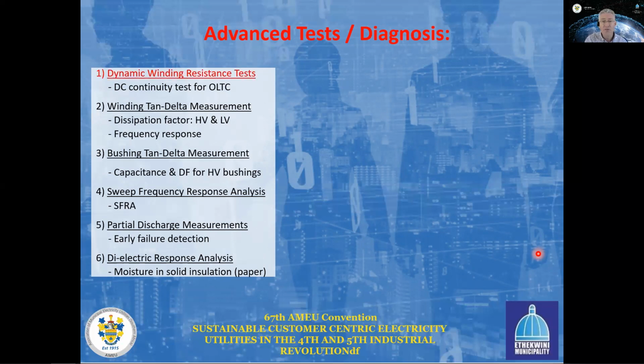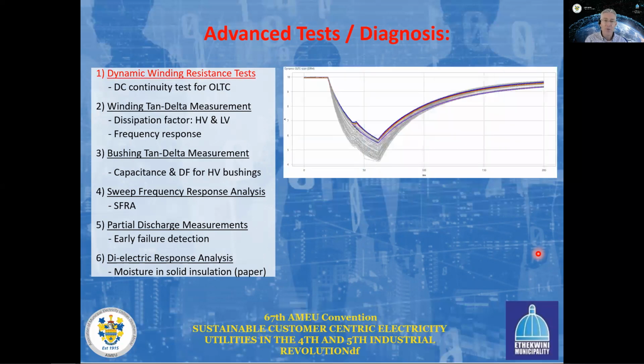And then we plot the response from those tests on top of each other. And here we can see the typical signature that we receive from a test like this. The signature meaning this is actually the DC current. And then we can see how the diverter resistors are switched in. This is the first diverter resistor, then the second diverter resistor, and then we have a discharge cycle where a certain winding is either added or switched out, and then the current discharges in that case.